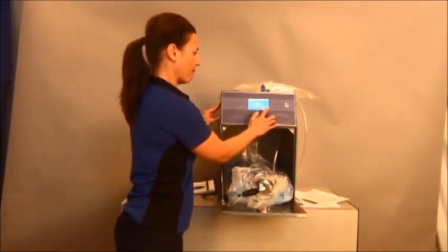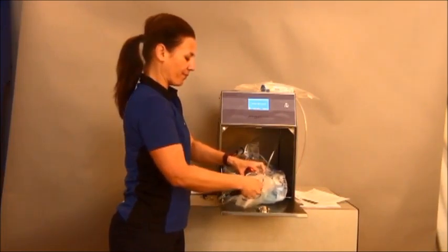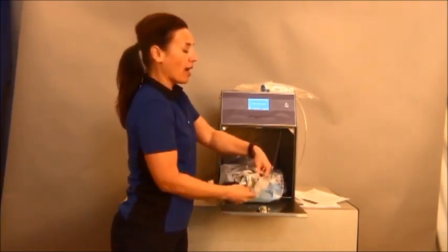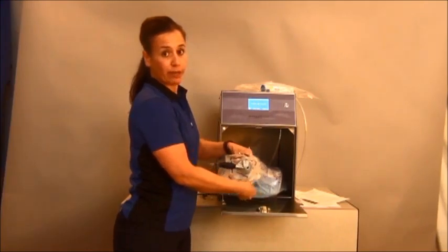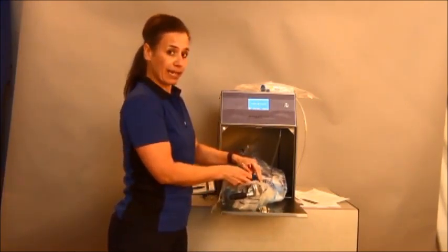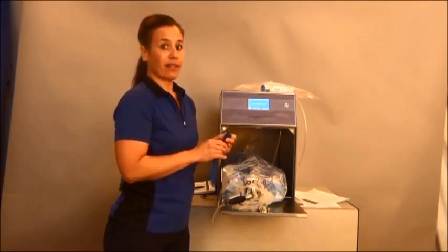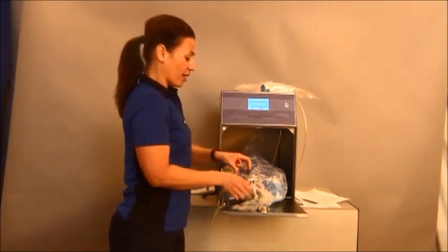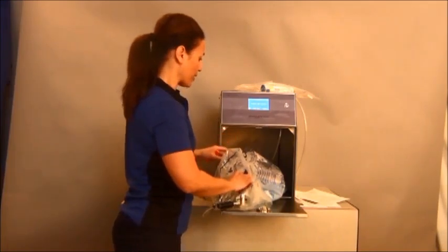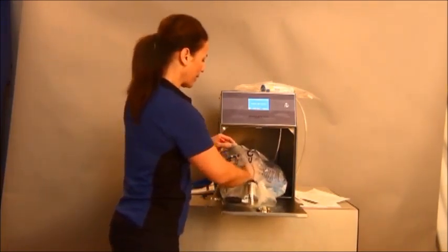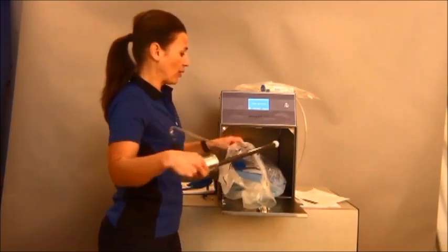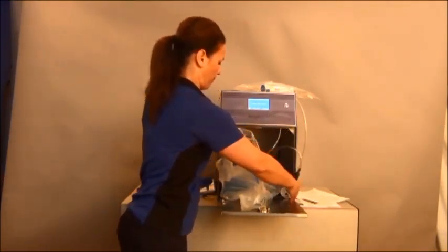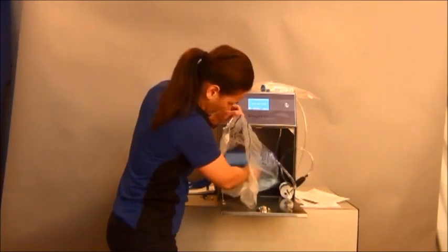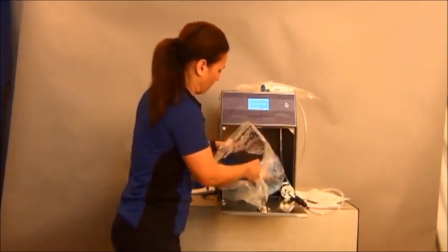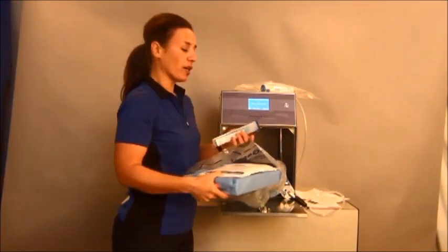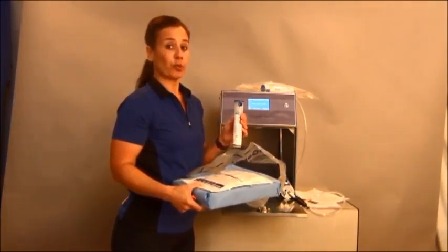So at this point in time, pressing the exit button, the first thing I'm going to do is check my dosimeter, my chemical indicator, which shows me that the proper concentration of gas during the sterilization cycle, as well as time of the sterilization cycle, was successful. Your gas cartridge can be disposed of in your normal trash.